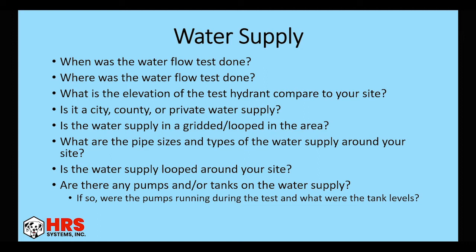Then if someone is supplying the water flow test for you, you need to know when it was done, where it was done, what the elevation of the test hydrant is compared to your site. Is it in a city, county or private water supply? Because these could all change how your water is delivered to your site and the supply. Is the water supply in a gridded or looped system around your site? Again, this can change how your water supply is provided to your site and whether you can come in from multiple directions.